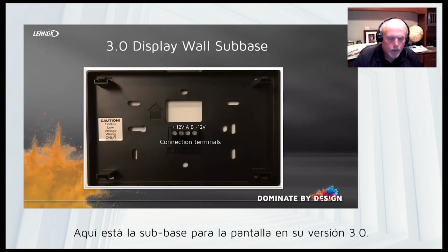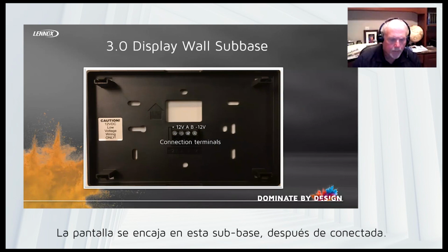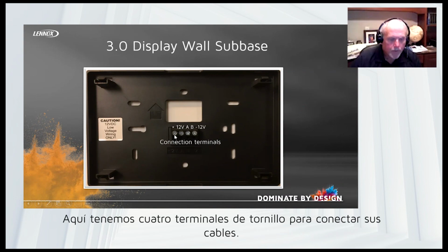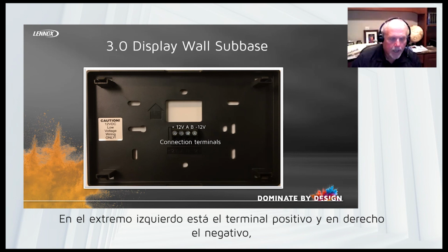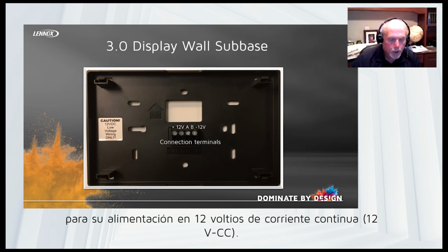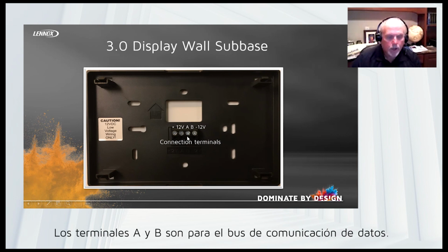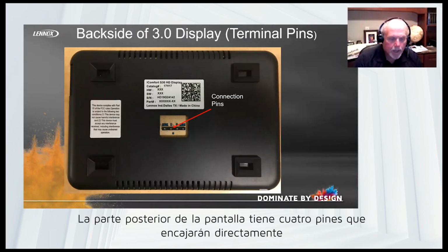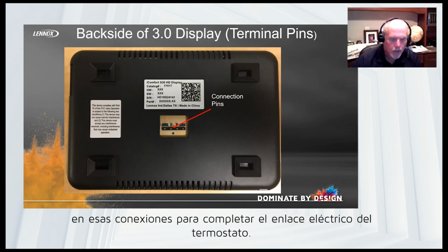Here is the 3.0 display wall base, the sub base, and this is what the display will snap onto after we get it wired up. As you notice here, we have 4 lug terminals to hook up your wiring. The far left one is your positive, and the far right is your negative for your 12-volt DC voltage. The 2 middle ones are your A and B, which is your communication bus. As you can see, the back of the display has 4 pins that will snap right into those lug connections to make the electrical connection for the display.